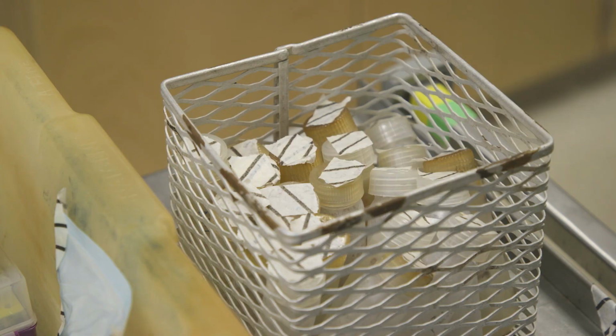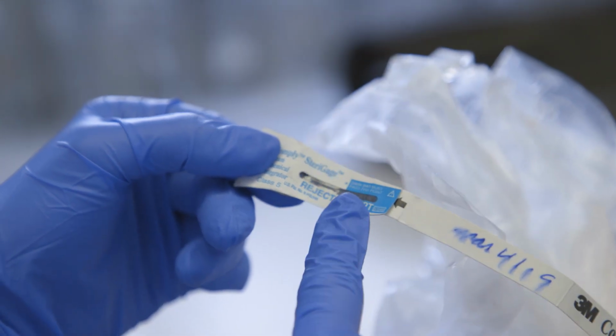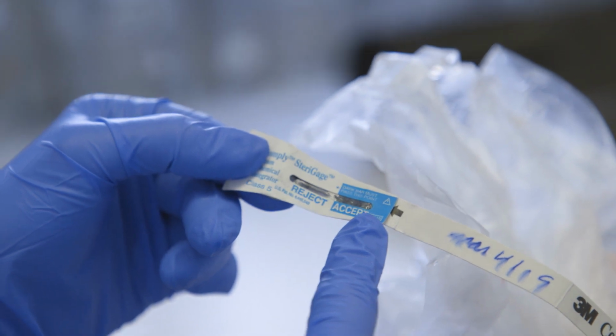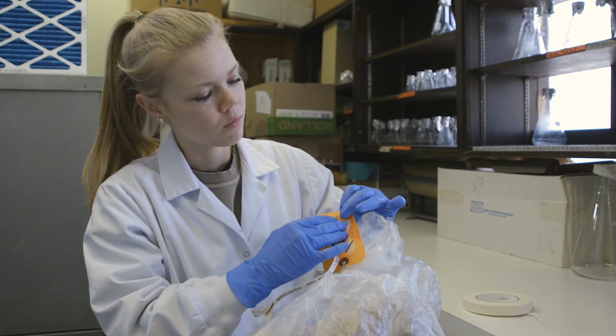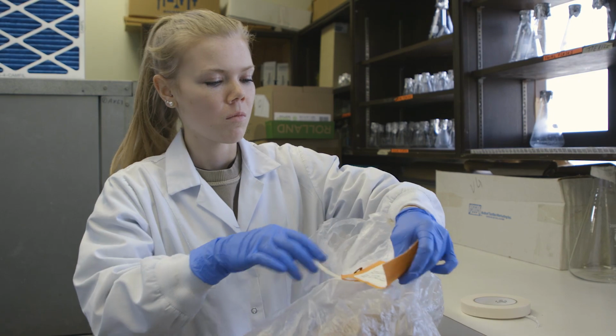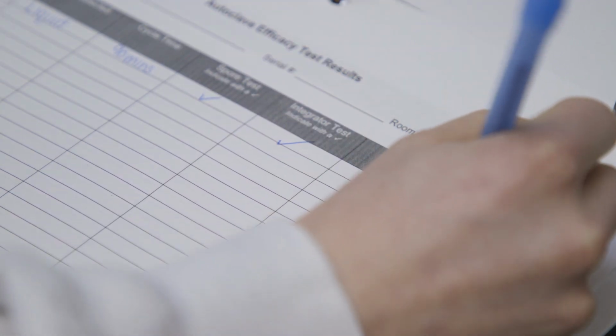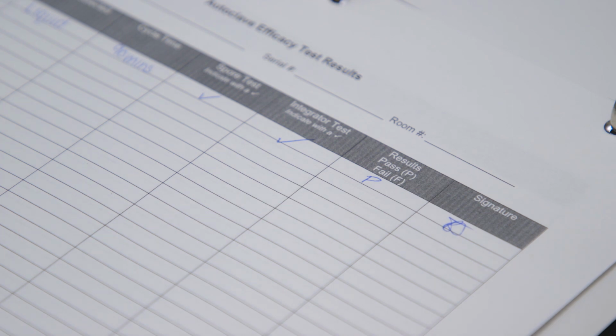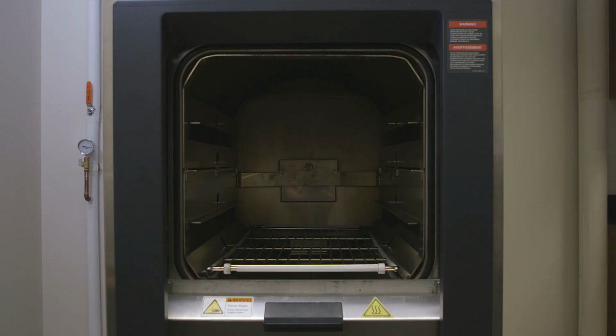For waste, ensure that the integrator strip in the biohazard waste bag indicates that your load was decontaminated. Attach the integrator strip to the back of your biohazard tag. Record the results of your integrator or indicator in the logbook. This is a simple pass or fail result. Before walking away from the autoclave, look inside to make sure nothing has spilled or been left behind.